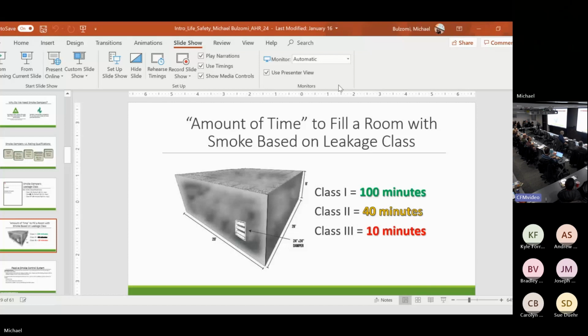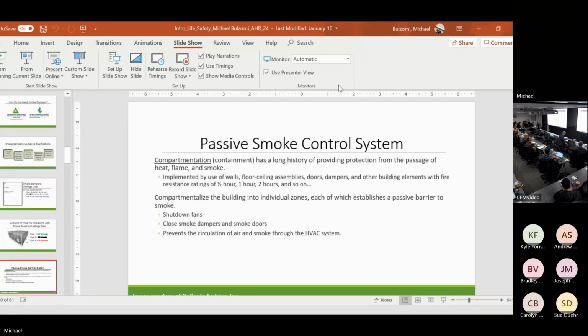This class 1, there's no building code requirement to specify class 1. You're going to use them in hospitals. You're going to use them in institutional isolation rooms, places where people cannot leave and you're defending in place. This is the most amount of protection you're going to get out of a fire smoke damper. It's the lowest leakage rating. So the room will fill up with smoke in 100 minutes. So if it was in the hospital, I could finish watching Jeopardy, eat my pudding, and still get out of the hospital. Right? So what's the difference?